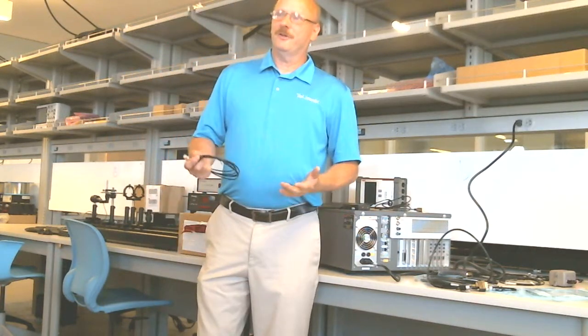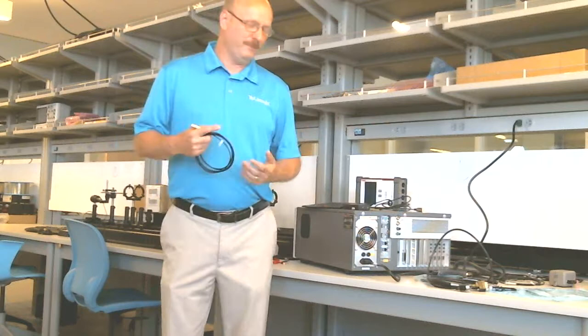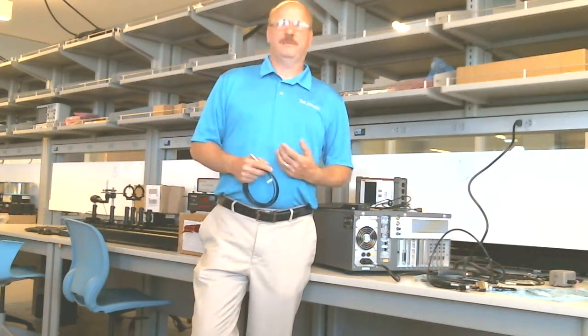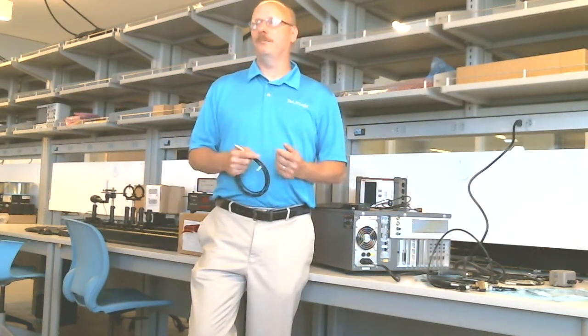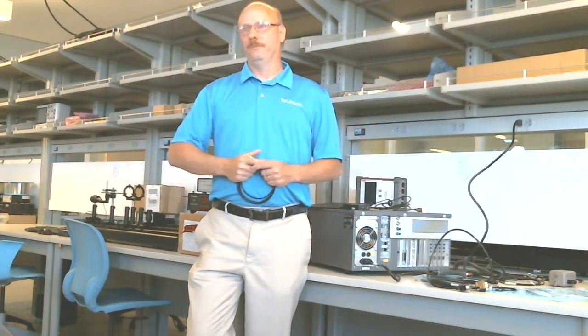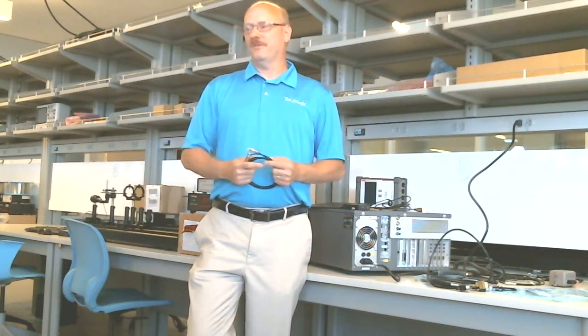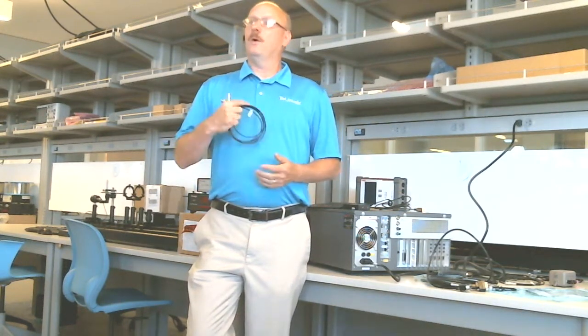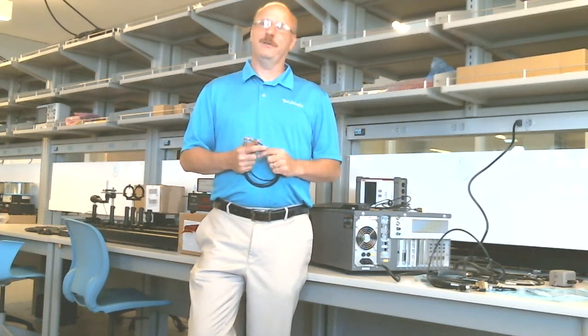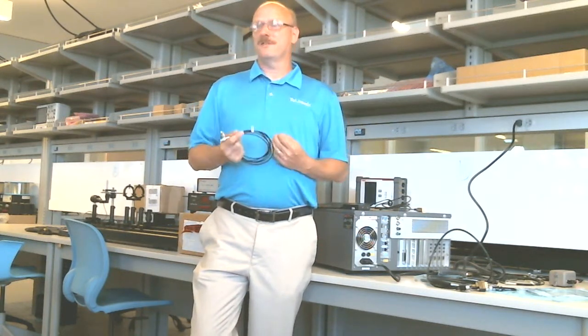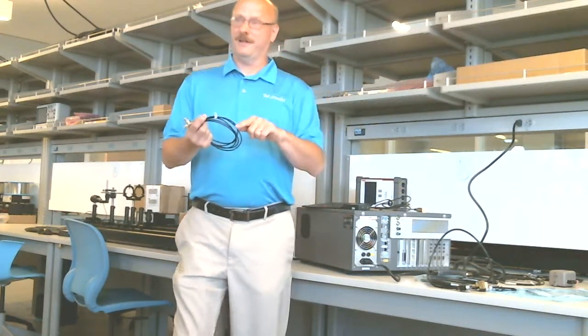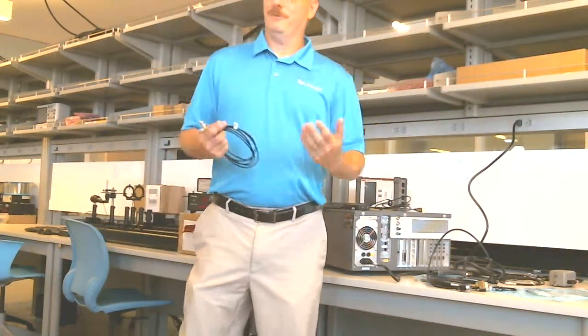So why do I need a triax cable? If you're measuring currents in the 100 nanoamps or above, throw these away, you don't need them. But when you start measuring below 100 nanoamps, there are error sources contributed by the cables that will swamp out your measurements.